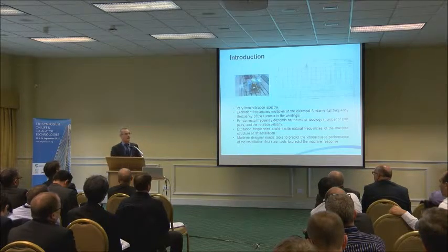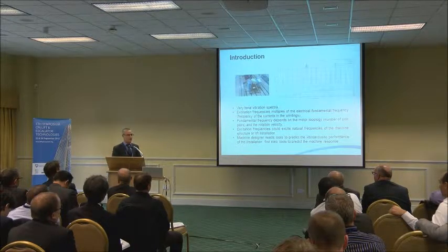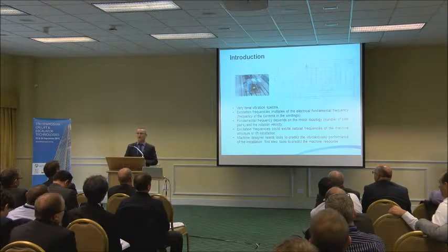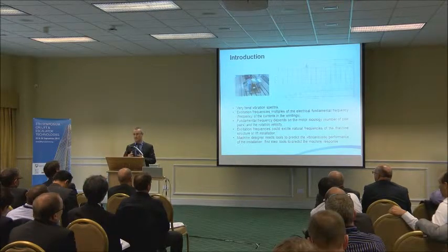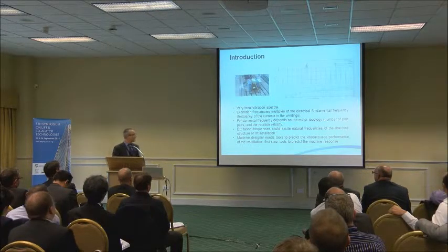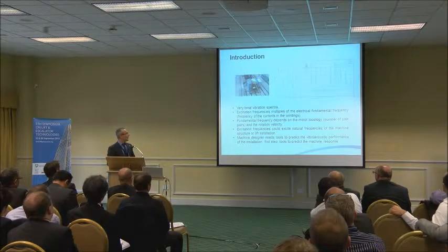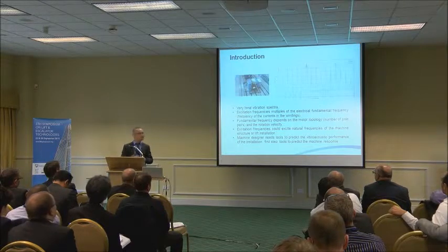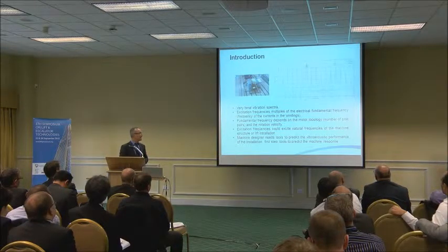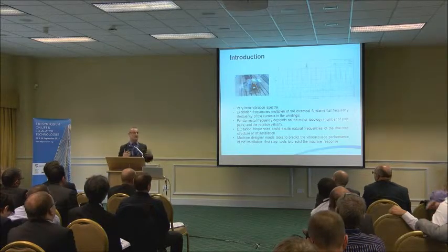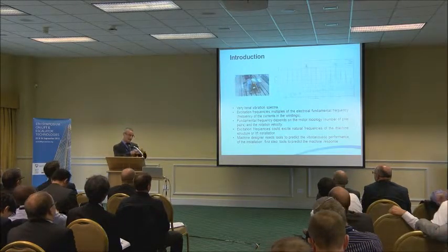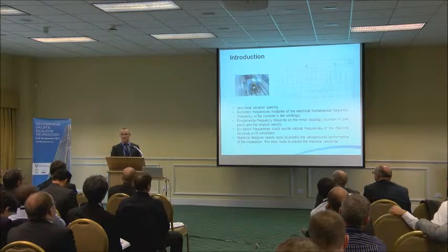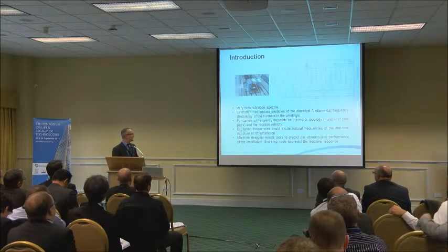I'm talking about permanent magnet synchronous machines, multiplied by the number of pole pairs. So we usually have peaks at those particular frequencies, and as we saw in the previous presentation as well, there could be resonance problems in the machine itself, and in the whole installation as well. So they must be avoided.